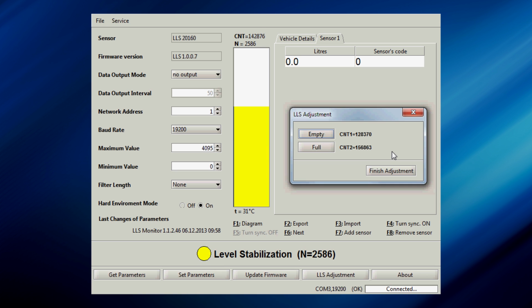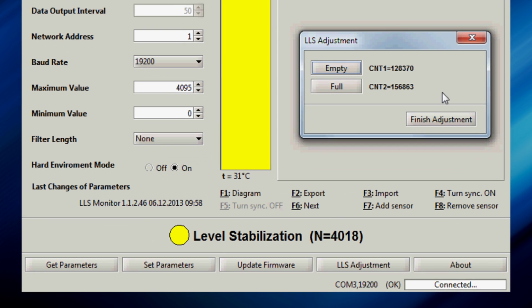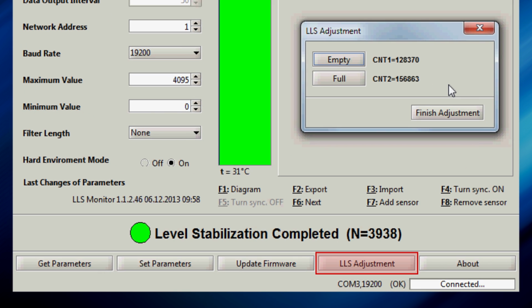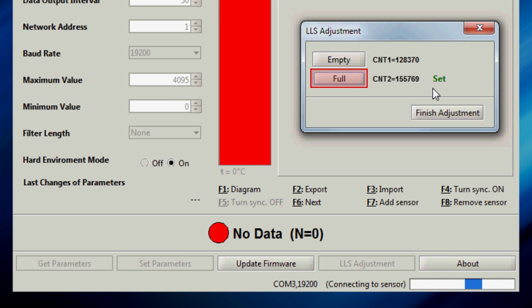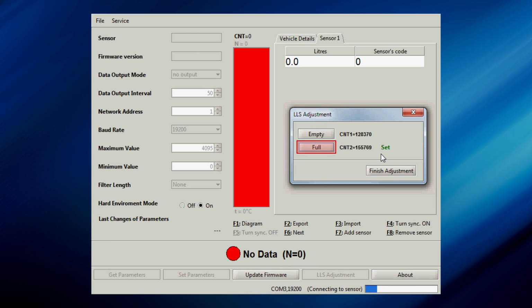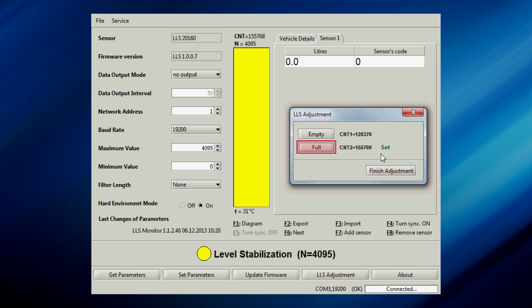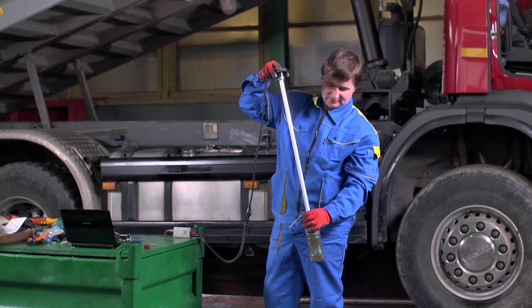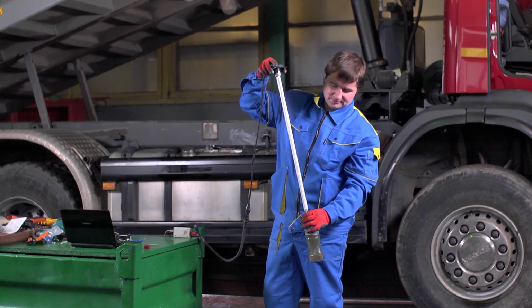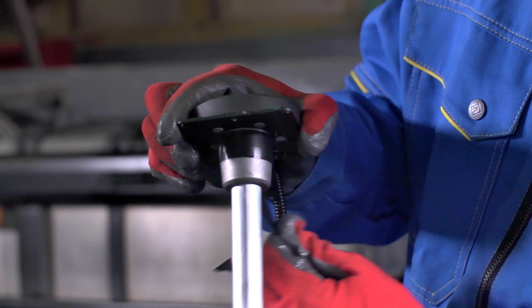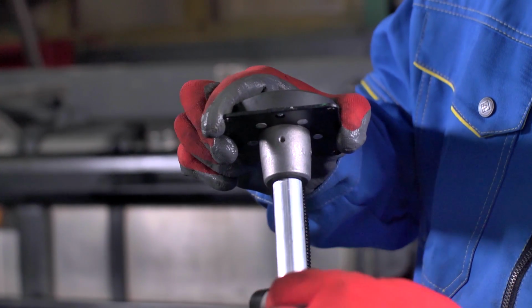After filling the sensor probe with fuel, wait for the fuel level to stabilize in the LLS Monitor application, and then click the full button in the sensor configuration section of the application. The new setting will be saved in the sensor memory. Then drain the fuel from the sensor probe. Remember to open the air vents of the sensor before draining the fuel.